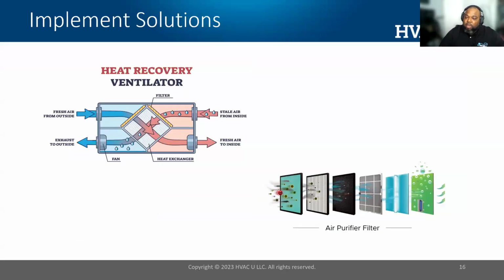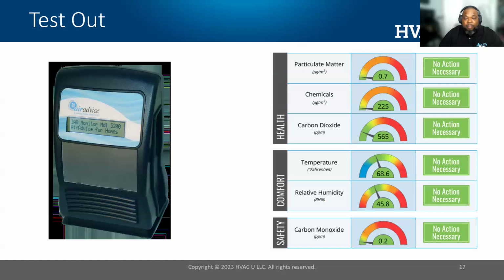Once we establish our reference point, we come up with an IAQ solution. That solution could be a heat or energy recovery ventilator to bring in fresh air. It can be enhanced filtration or maybe an air purifier. Once we solve the problem, we test out. This is an actual example: the image you saw before and this image are the exact same property after we've implemented a solution. So with IAQ, that's the name of the game: measuring it, fixing it, and then testing and verifying that you fixed it appropriately.